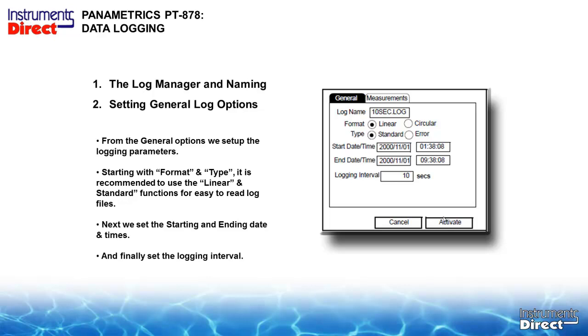Now we need to start and set up the log. So here we're going to set up the format type. Recommended to use linear and standard. It's easier to read the log files. And next we're going to set the start and the ending date and times. So in this case, give yourself a little advanced time. Don't say I'm going to start in 10 seconds. So give yourself a little start time, and you can actually practice a log on your desk if you feel uncomfortable with that before you go into the field. So your start time you put down, your end time you put down there, and date.